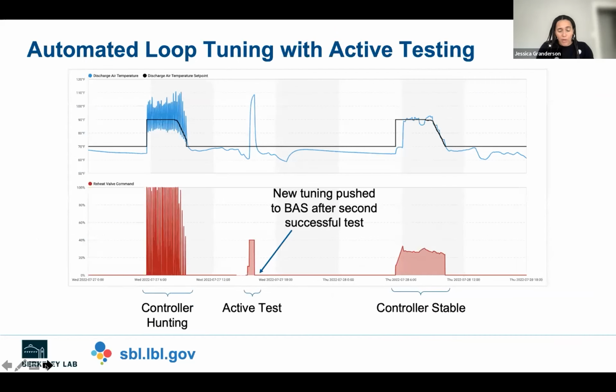The third example I want to show, so those first two are kind of in that optimization category. We're finding problems, we're improving energy consumption by ignoring the rogue zones, and we're implementing the very best in class reset strategies. This is an example of correcting a fault, the hard fault being hunting from a controller. So we're automating the process of tuning the PID loops here.